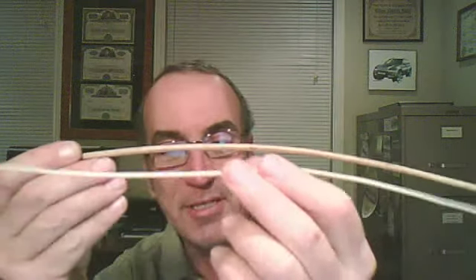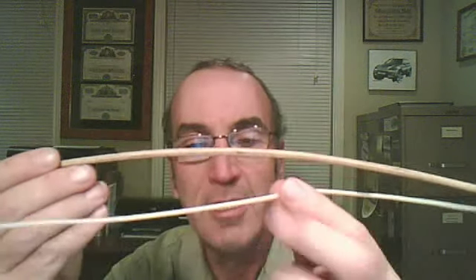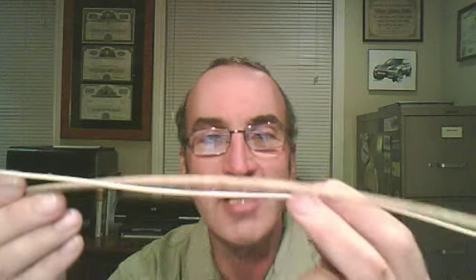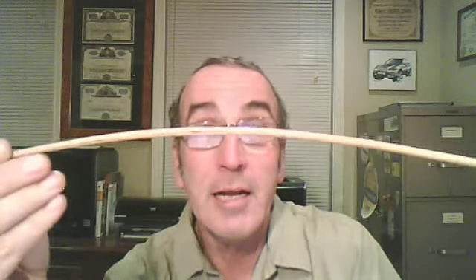Now, the problem with this wiring right here. First, let me show you this. This is a piece of the new wiring that we put in today. This is just a single strand out of a Romex conductor. It's almost half the size. But look at this wire here. 1930, this is 70, 80 years old. Watch what happens when you try to bend this.